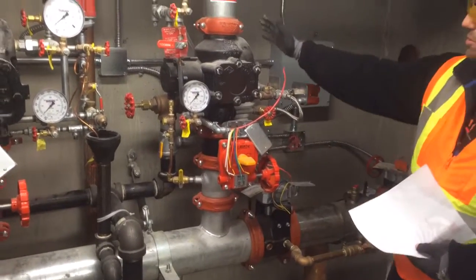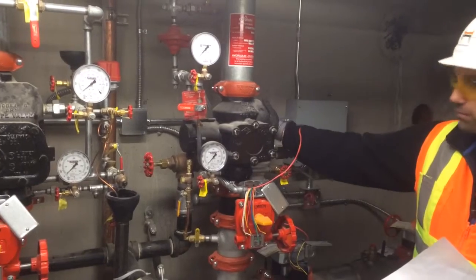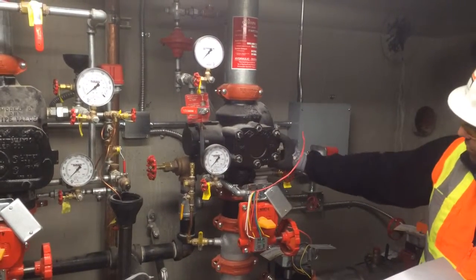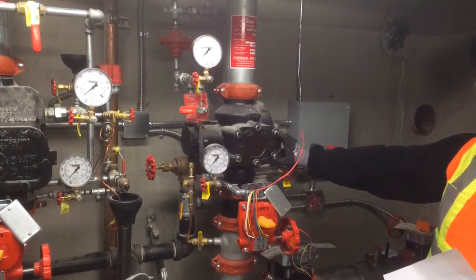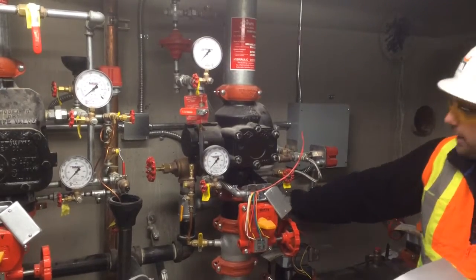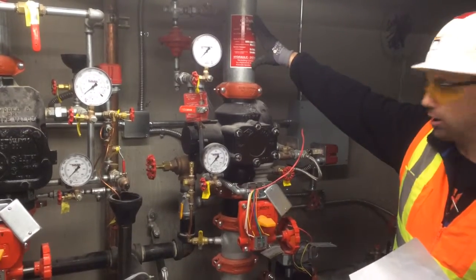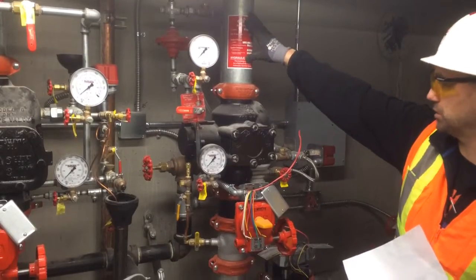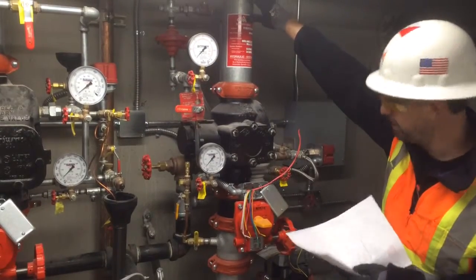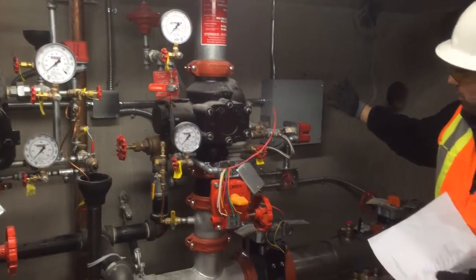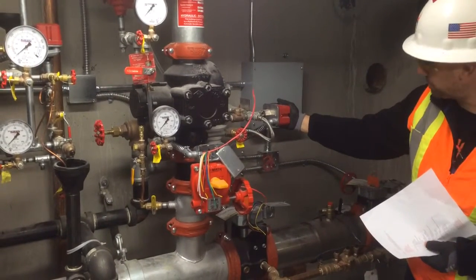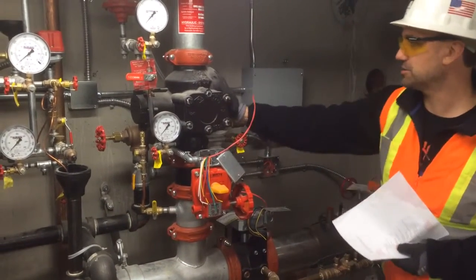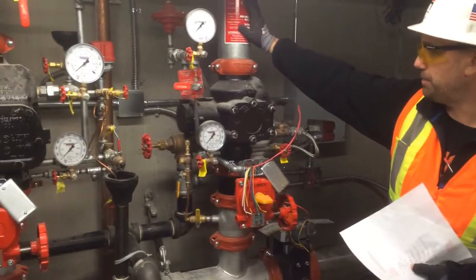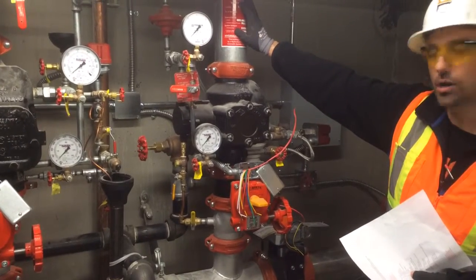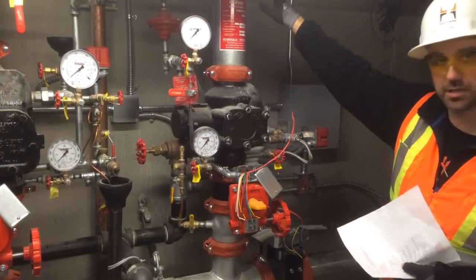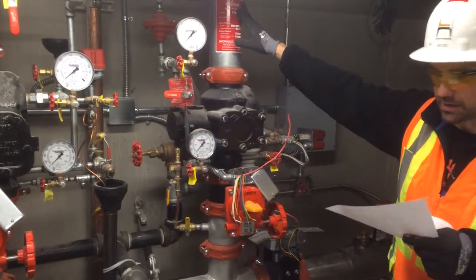And then this system has dry valves. This dry valve has a reservoir of water inside of it, and what it does is it holds the water back on the wet side and keeps air on the air side, and when this air is released, it floods the system with water. These systems all have pressure switches. So this is a pressure switch, and it monitors the pressure inside this dry valve and on the dry piping, so it can tell the fire alarm when this air has been released, and that signals an alarm.